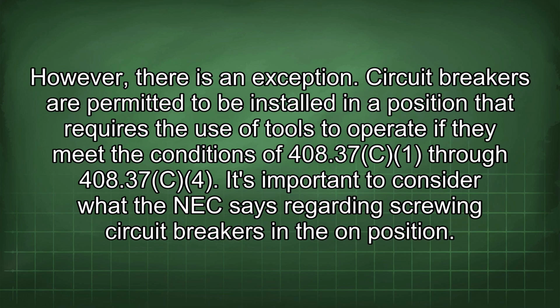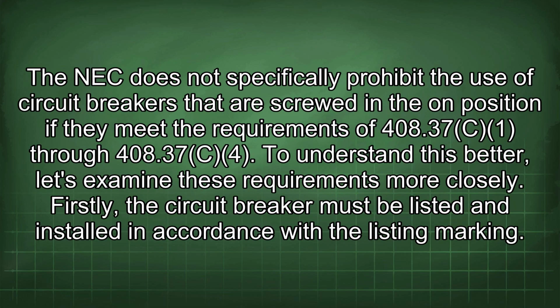Circuit breakers are permitted to be installed in a position that requires the use of tools to operate if they meet the conditions of 408.37c1 through 408.37c4. It's important to consider what the NEC says regarding screwing circuit breakers in the on position. The NEC does not specifically prohibit the use of circuit breakers that are screwed in the on position if they meet the requirements of 408.37c1 through 408.37c4. To understand this better, let's examine these requirements more closely.